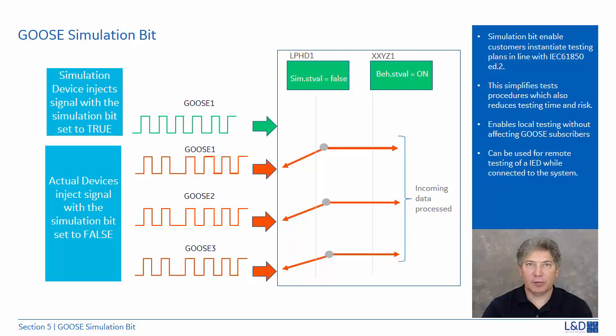For the testing of part of a scheme that is affected by the modification, it is possible to do the remote testing using the testing features from IEC 61850 Edition 2: the simulation bit, the GOOSE message, and the different modes of the tested function elements. This supports the ability to remotely test a subset of functions and their elements while keeping the rest of the system in operation.